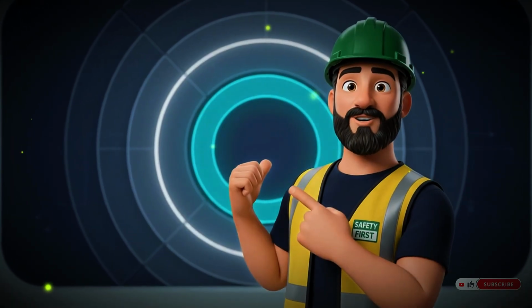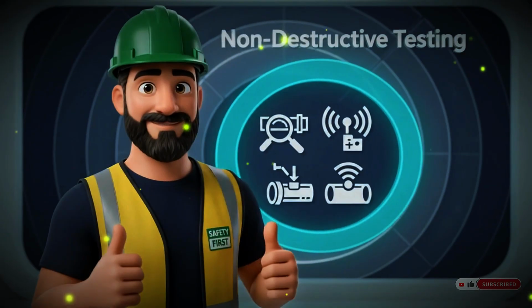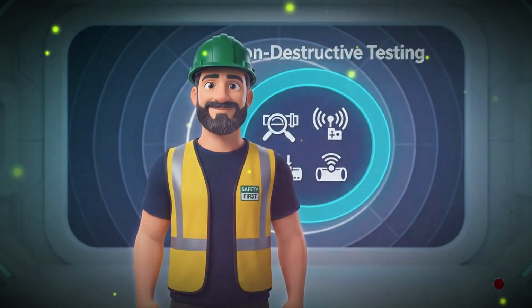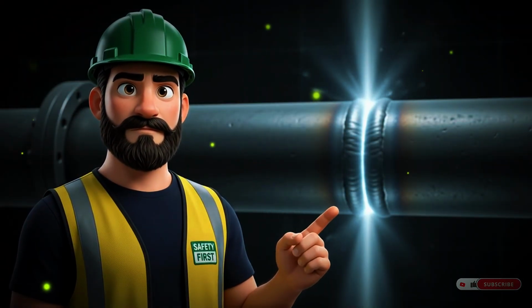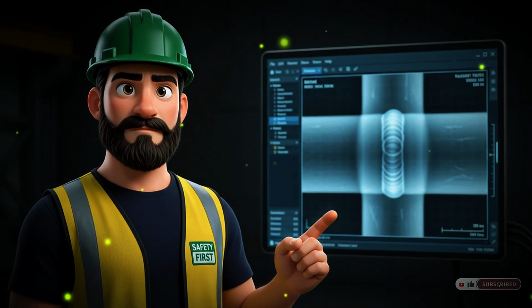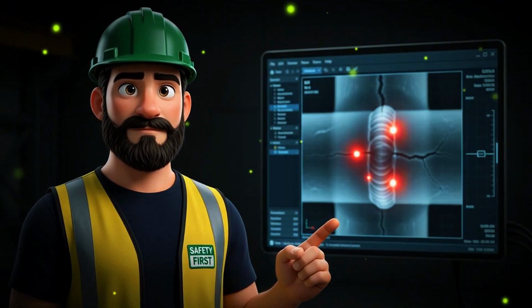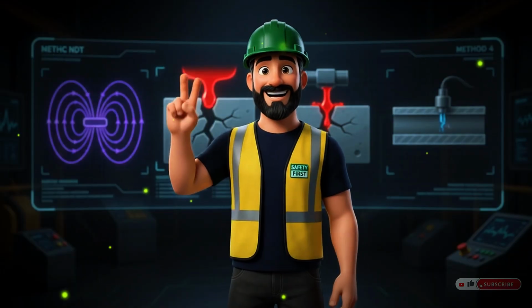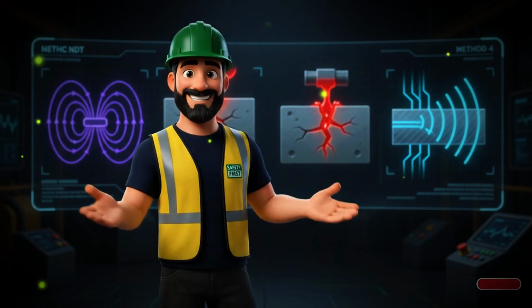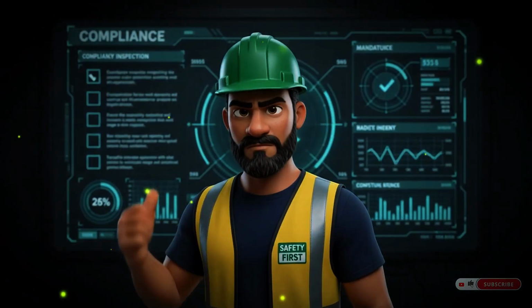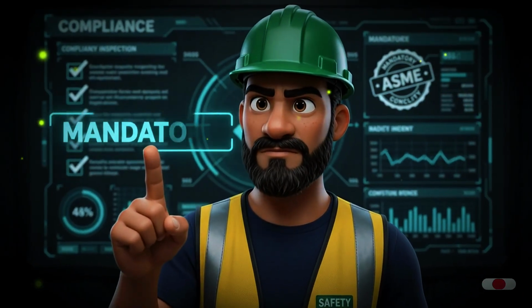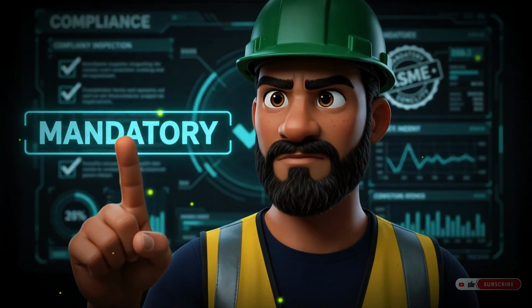The second layer is non-destructive testing, covered by ASME Section 5. Industrial radiography to verify the internal integrity of welds without destroying them. Ultrasound to measure wall thickness and detect internal discontinuities. Magnetic particle testing and liquid penetrant inspection to identify surface cracks. These tests are not optional, they are mandatory before any pressure vessel enters service for the first time. And API 510 requires them periodically throughout the entire service life of the equipment.